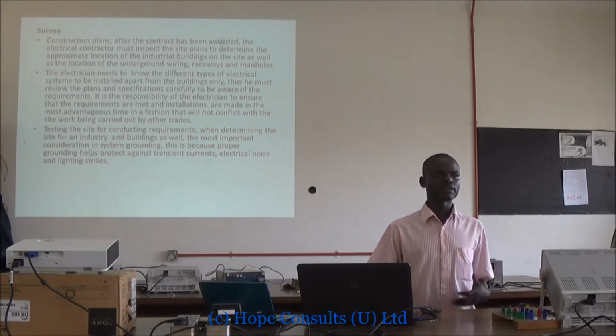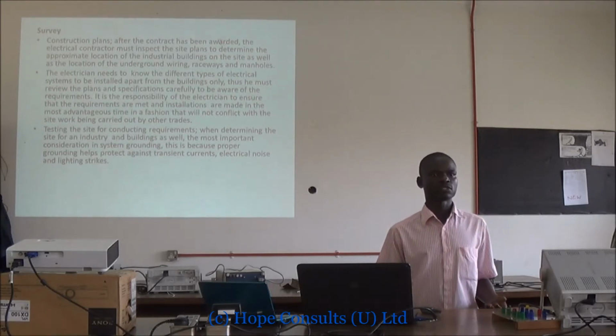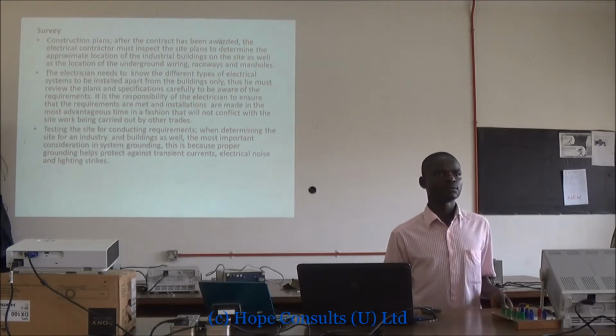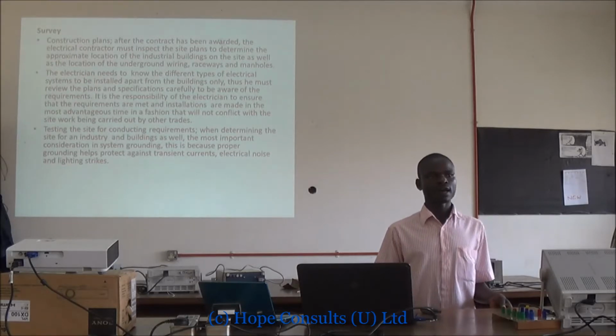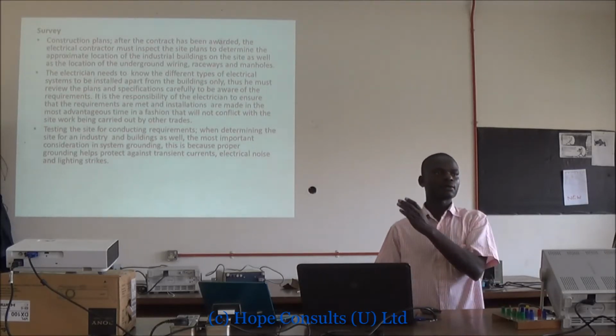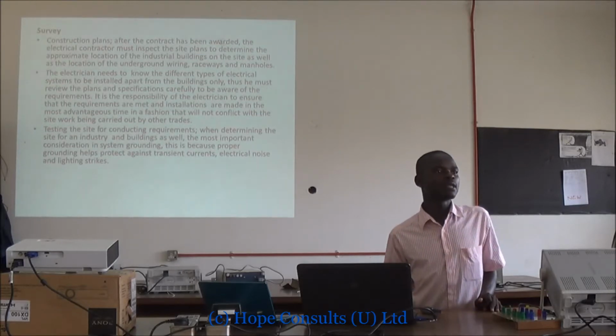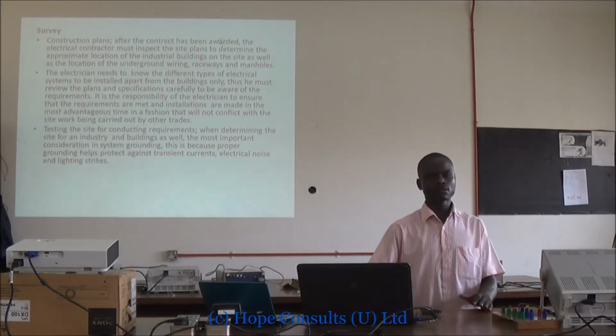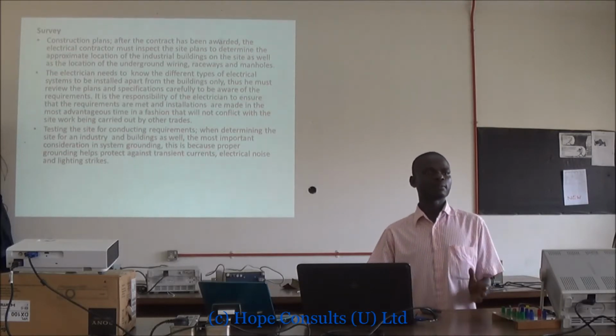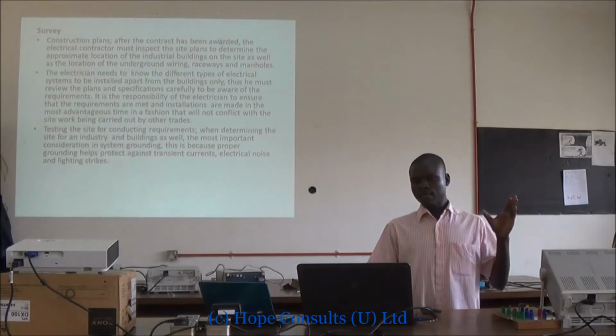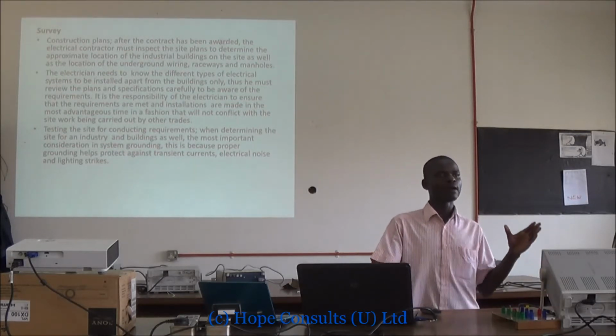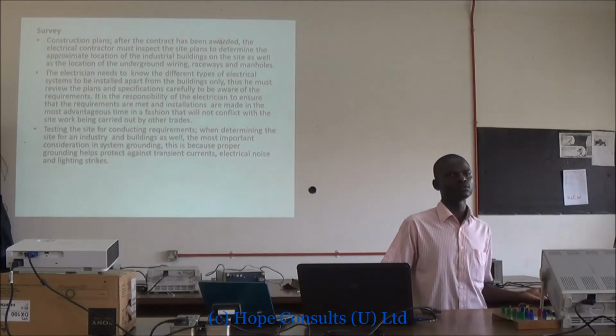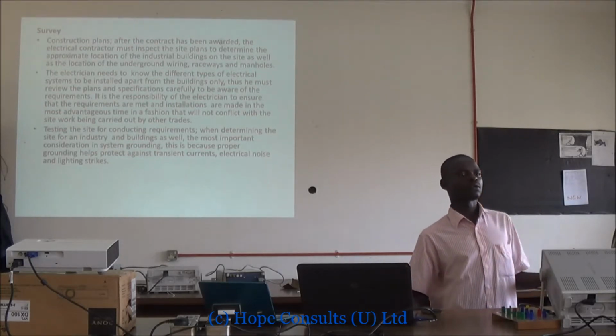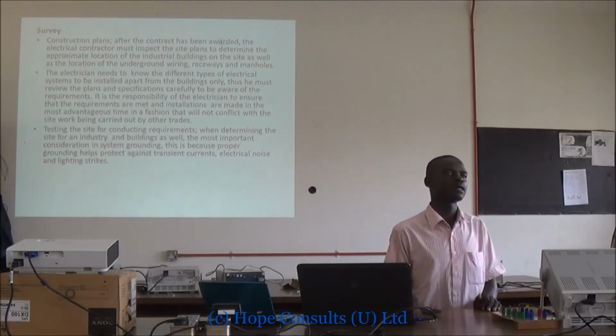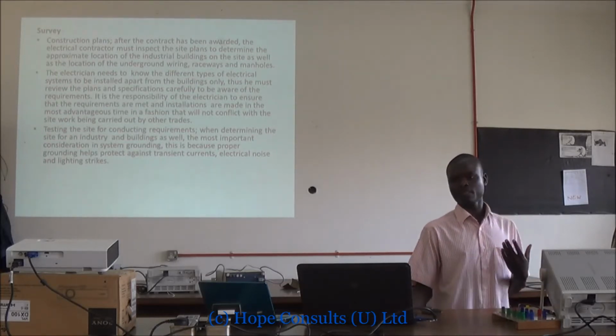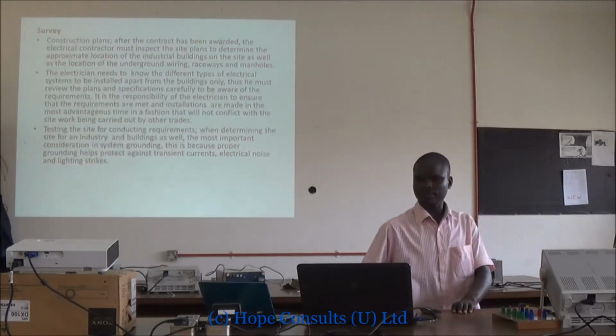Like for instance, where you find that there are some belts used for applying mechanical forces to move the motors, you realize that there are some charges which are induced. So to reduce those charges, there must be earthing. This earthing must be considered because the grounds have got very many different conductivities varying from place to place. So the electrician or person concerned must make sure the places are investigated to realize where to apply the earthing for safety. Because you may apply earthing in a place which is not all that conductive and realize there is leakage of power, which might be dangerous to the community as well as the workers. So I think, thank you for listening.